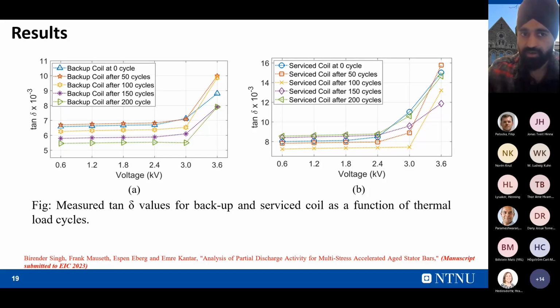So 50, 100 and 200. Because they have been kept in a storage place for a long period of time, they have moisture content inside them, and that is clearly justified by observing the tan delta values from 0 to 50 cycles. Their values are quite high, near about 7 into 10 to the power minus 3, that is the blue and orange colors for the initial cycles. But as we keep on increasing the cycles, that moisture content has evaporated and the tan delta values keep on decreasing.